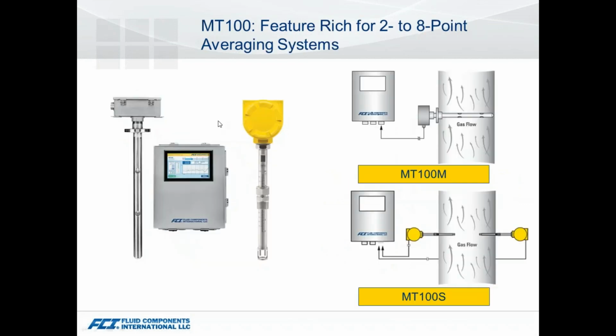Now, when you go to the MT100 here, we've got a couple different options. We have the option to use a single point sensor like we saw on the ST102. And with that, we can go 2 to 8 points depending upon the duct size and the accuracy we're trying to achieve. The other option, again, is going to a mass style.